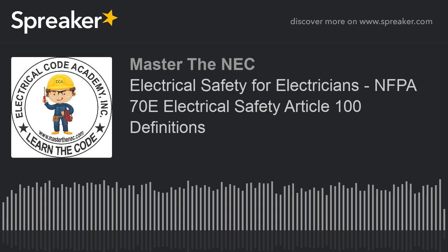So a lot of equipment and a lot of different suits and a lot of different things will have an ARC rating on it. So we got to make sure that we at least cover the ARC rating statement. And what is it? It says the value that's attributed to materials that describes their performance to exposure to an electrical arc discharge. Okay, you have a bolted fault, you have this discharge, and you have an ARC rating that gets attributed, and it can be based on an ATPV, which is the arc thermal performance value, or it can be based on what's called the EBT, which is, again, that one is ARC rating, and that is called the energy of break open threshold.